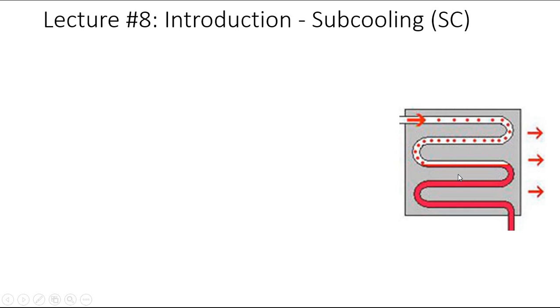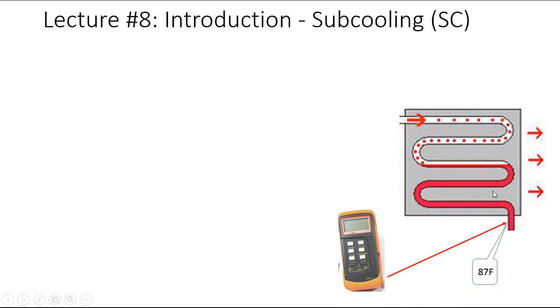I've just grabbed just that so we can kind of see what's happening here. So as we did on the superheat side, we're going to take a temperature measurement first. And where that temperature measurement comes from is on the outlet of your condenser. After we went into gas, it comes out as a high pressure liquid here. We are going to take a physical line temperature of this liquid line here, they call it. So the material, as we covered before, is the same thing as it is on the evaporator side. This is typically going to be made of copper.